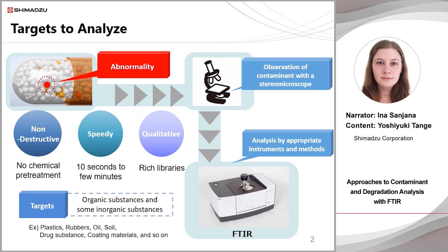Let's take a look at the workflow of contaminant analysis in FTIR. If you find an abnormal part in a sample, first collect it and observe it with a stereomicroscope. Check the condition and the shape of the contaminant. Then determine the appropriate instrument and methods for analysis.